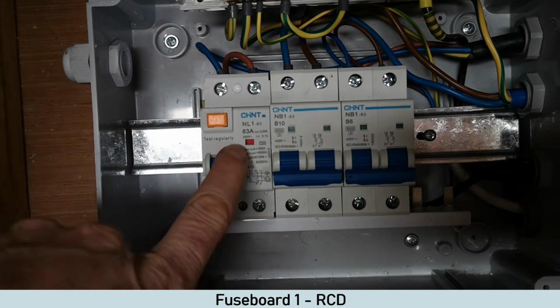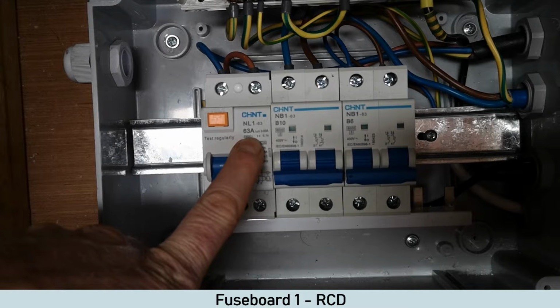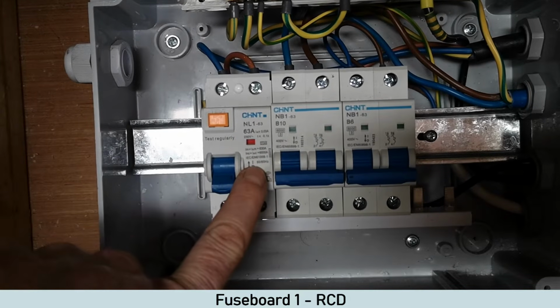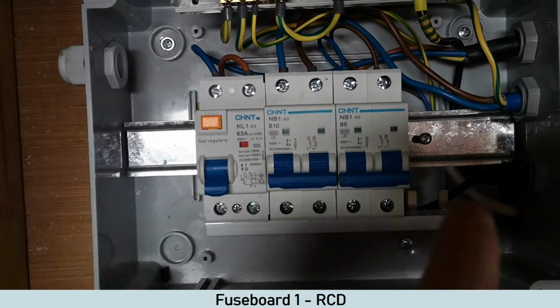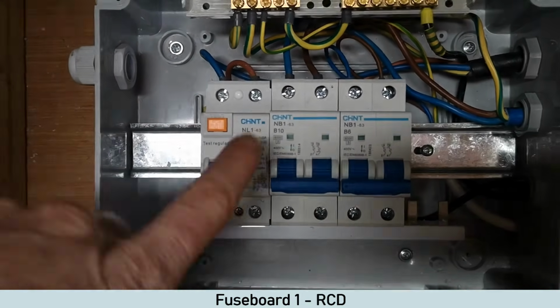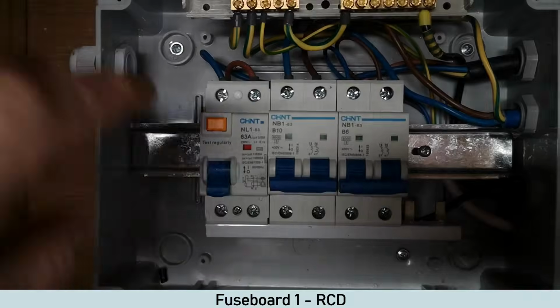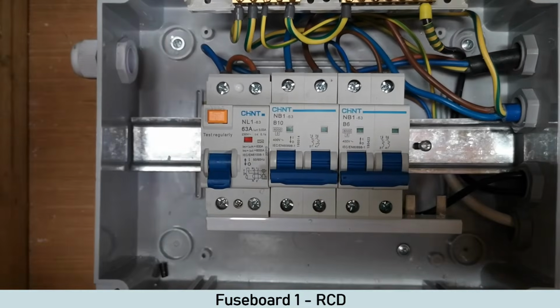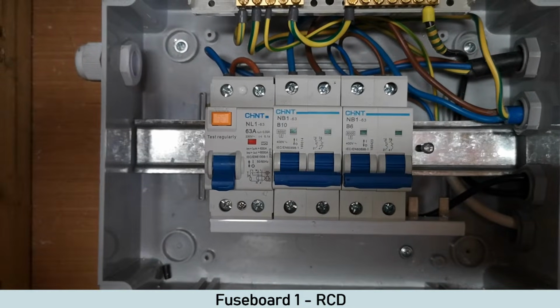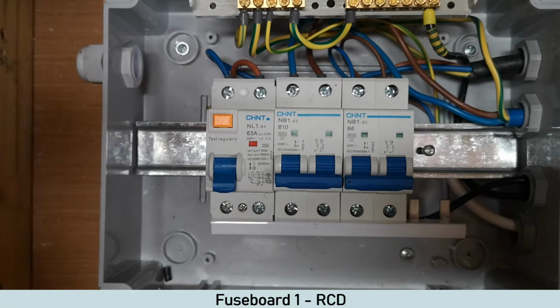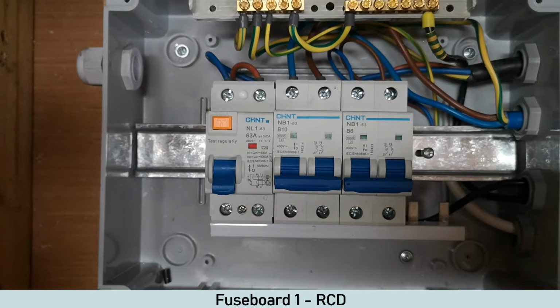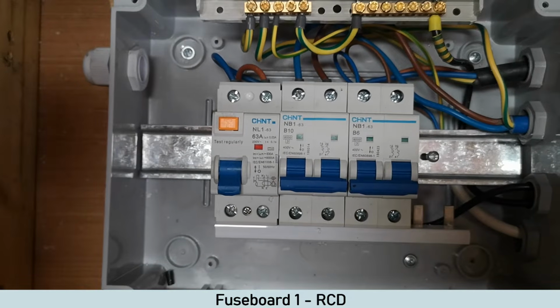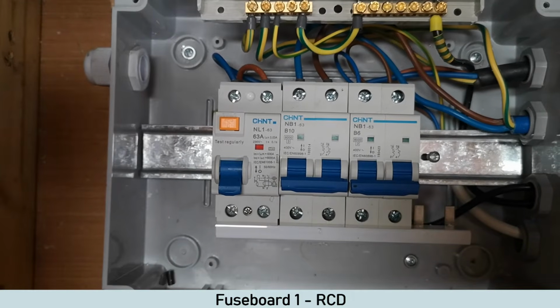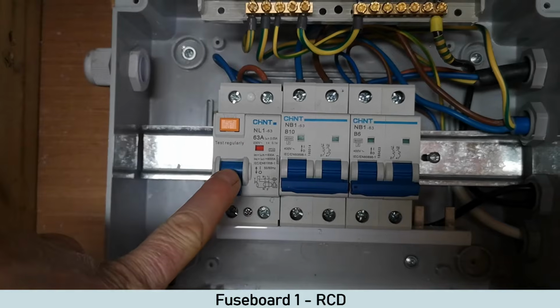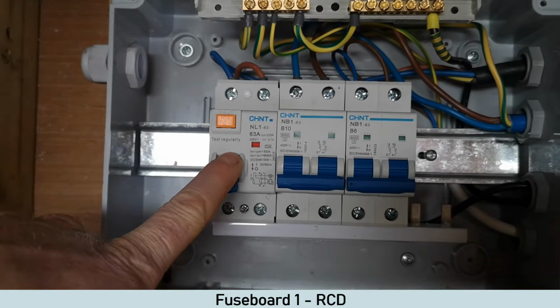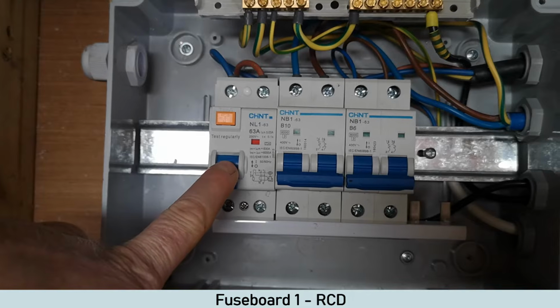Our RCD is 63 amp. That's fine. It doesn't really matter with the amperage with these. This is here specifically for fault protection and isolating these circuits here. The RCD is rated to 30 milliamps. Now that is in the regs and that is the maximum in the regulations, so it can't exceed 30 milliamps. The reason for it not exceeding 30 milliamps is because that's what they class as heart stop current. It doesn't mean you won't get a shock. You still get a bit of a shock, but it means that it's going to cut out before your heart cuts out. And the other note to add on this is RCDs have a type.